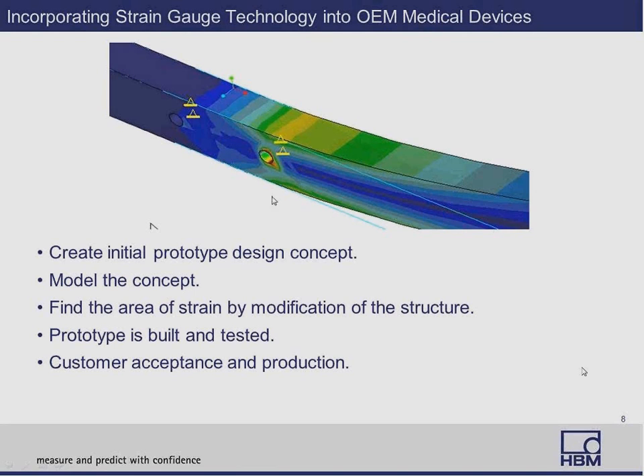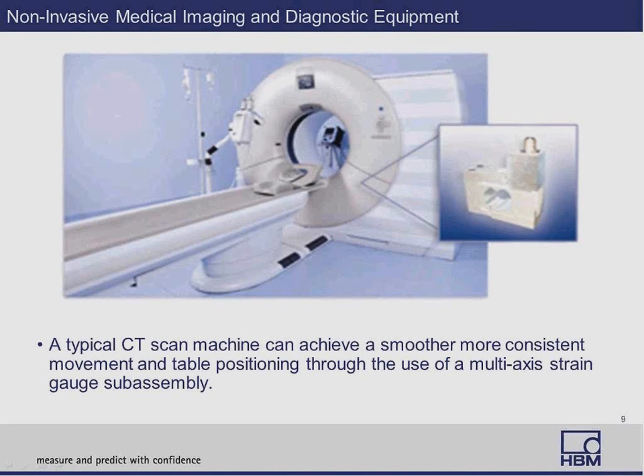That's basically how strain gauge assemblies work and are assembled. Here's a situation where an OEM of a CT scan machine was looking to control patient weight distribution, get some precision movement, and especially highly repeatable table positioning. That was achieved using a multi-axis load cell. One of the benefits is that you get better imaging and controlled movements, so you're not scaring the patient or putting the machine into a position where it won't create the proper image.